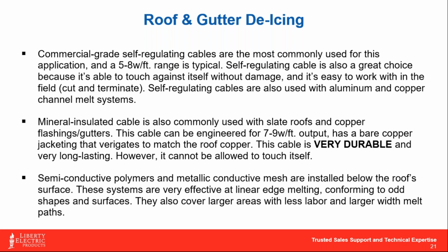The semiconductive polymers and the conductive mesh, what's really neat about those in the roof and gutter application is that they go underneath your shingles, so it's a hidden system. You don't see anything from the outside, which is really nice. But realistically, it makes for a tough install because your roofing guys are hinging on the installation of that particular system, and you don't want those polymers or conductive mesh products left exposed to direct rainfall or the elements. So generally you have to have the roofer and the electrician in perfect concert with each other to pull those jobs off for roof and gutter to be much more efficient.